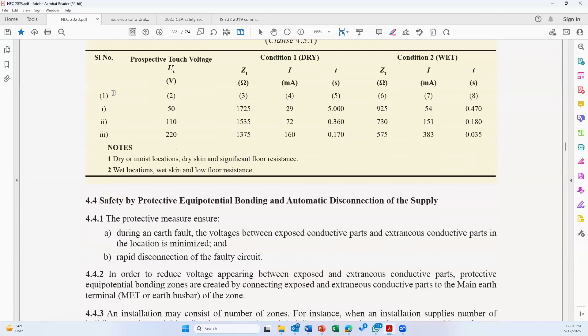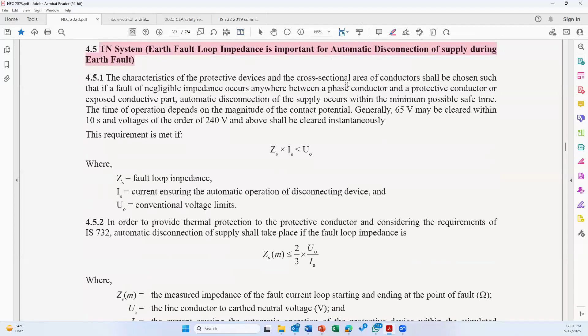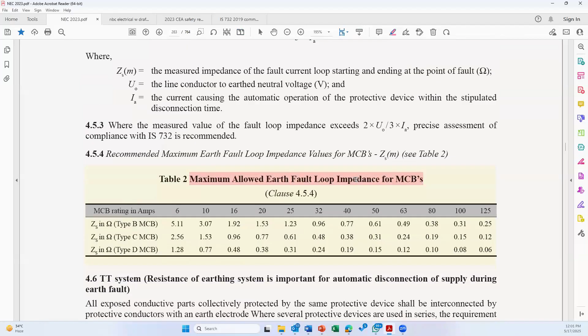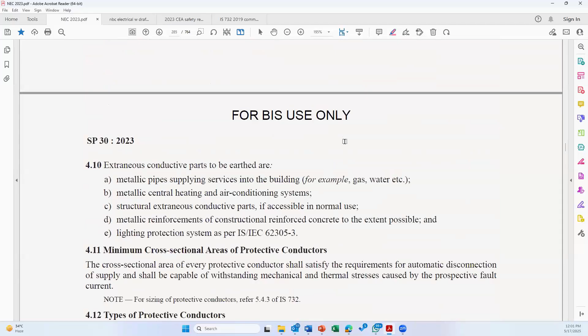Now, in NEC, we also made some beautiful calculations. For example, the requirement, the earthing of the installation, then the disconnection times are given, then how you should make equipotential bonding. And for example, in TN system, earth fault loop impedance is important for automatic disconnection of supply. The calculations are given. Maximum allowed earth fault loop impedance of MCBs is given. Basically, this information tells you that the correct safety measure against electric fault is protective equipotential bonding and automatic disconnection of supply. Number one, protective equipotential bonding: you must bond every metal part in this fashion, which I have shown, for example, in this particular picture. Number two, the automatic disconnection of the supply should happen because you have to keep the earth fault loop impedance below a certain level.